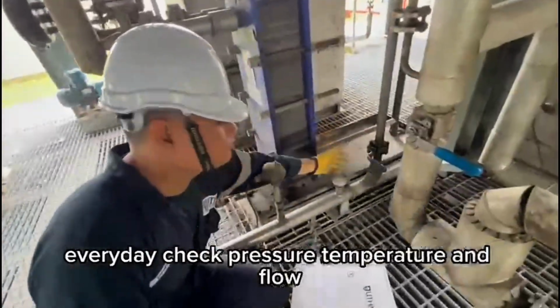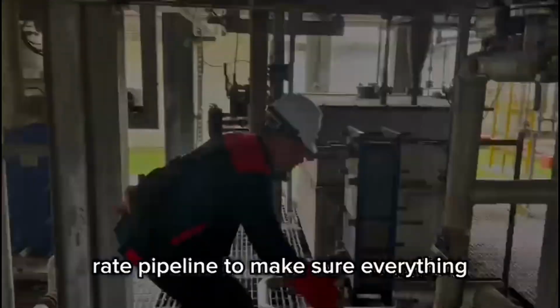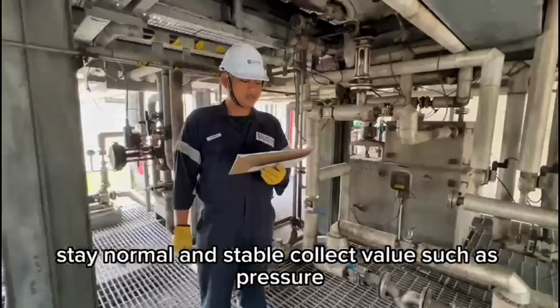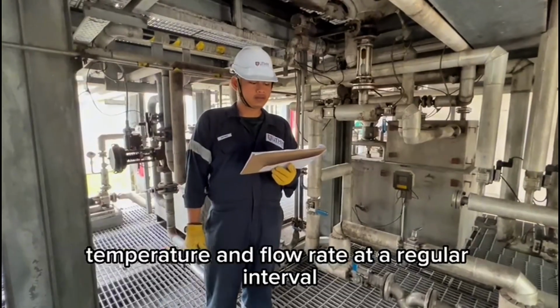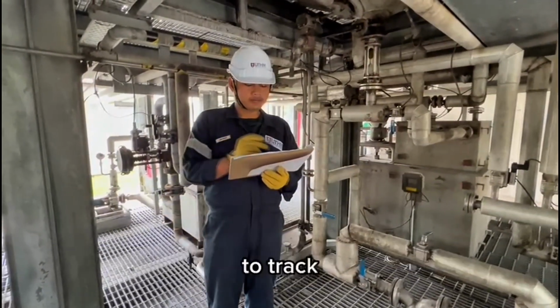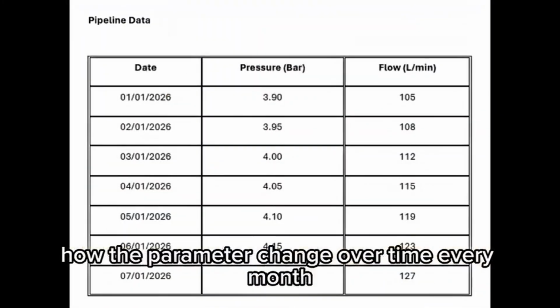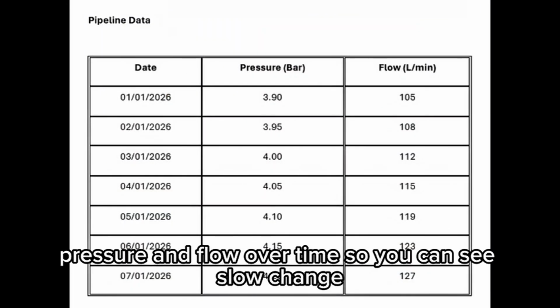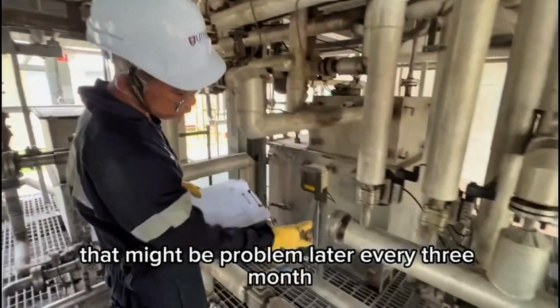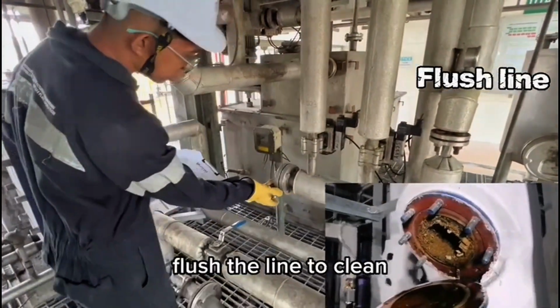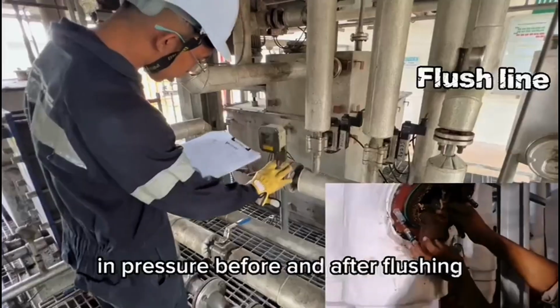Every day, check pressure, temperature and flow rate in the pipeline to make sure everything stays normal and stable. Collect values such as pressure, temperature and flow rate at regular intervals to track how the parameters change over time. Every month, look at the trend of pressure and flow over time so you can see slow changes that might be a problem later. Every 3 months, flush the line to clean the inside and check the difference in pressure before and after flushing.